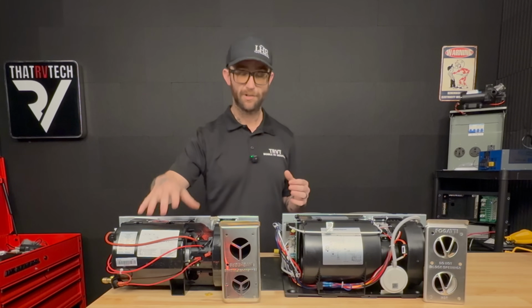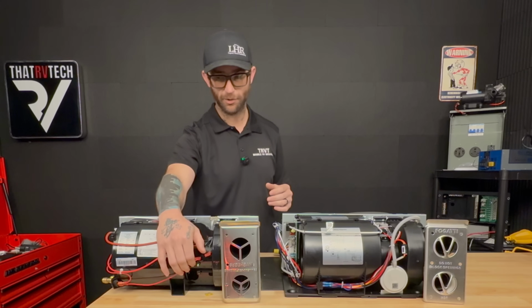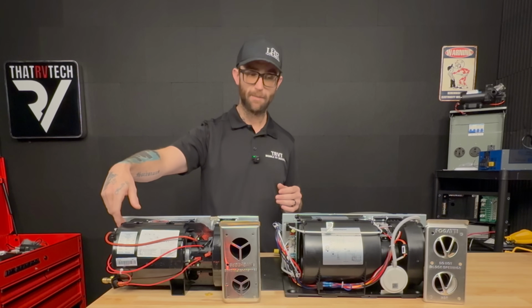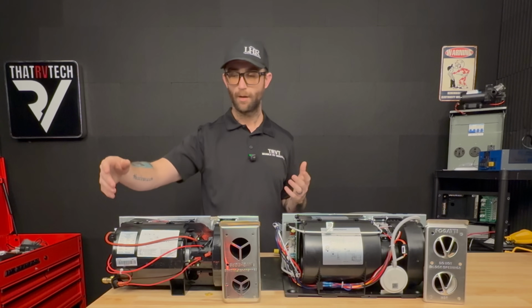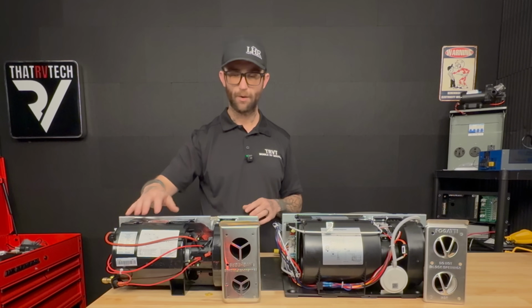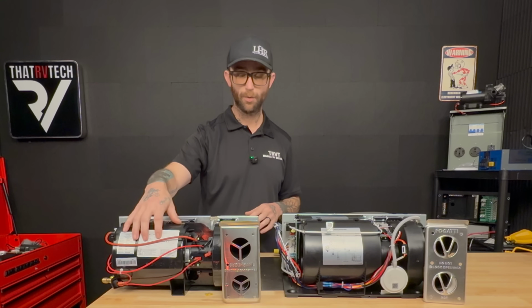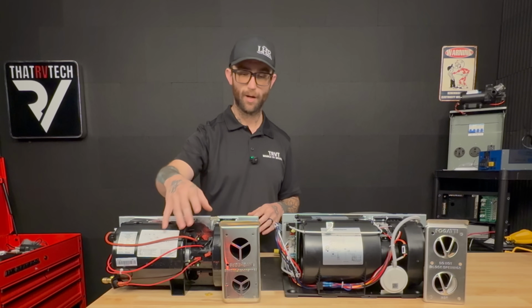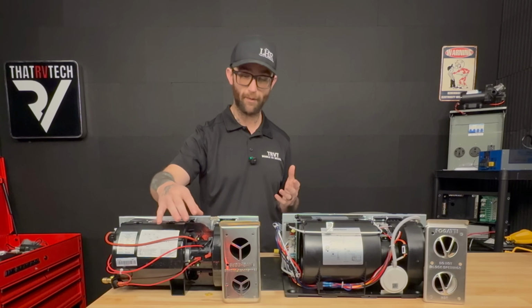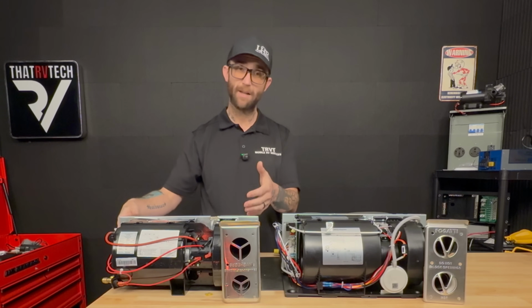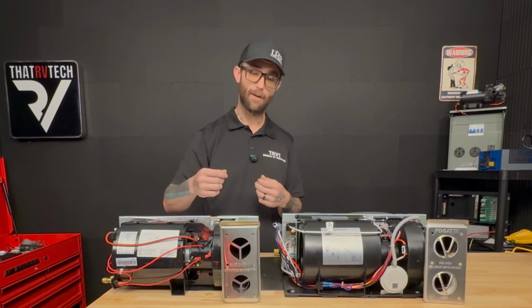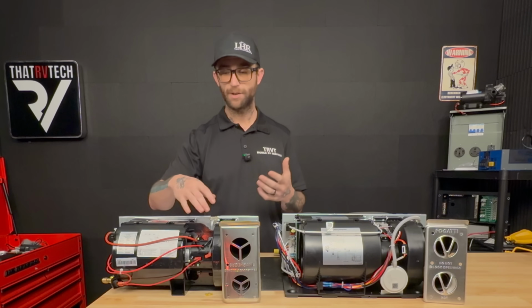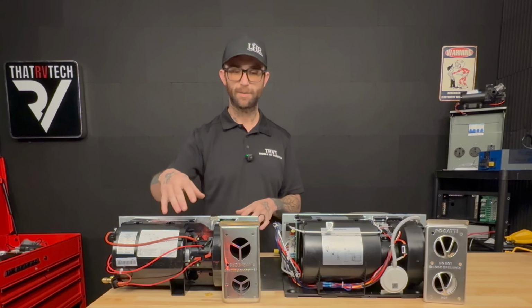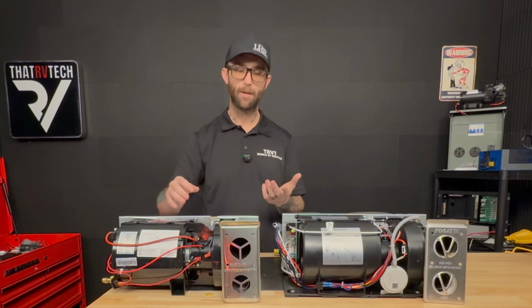Now, on a Suburban, yeah, you can access the sail switch. You can get your hand back there and get to the control board. That's about it. In order to, say, change a blower wheel, I've got to pull this whole front cover off. In order to get the motor out, to finalize that, I have to get to the bottom side of this furnace to disconnect the ground wire. Pretty much anything you want to change out in here besides a couple little things here in the front, you've got to pull the whole core out.